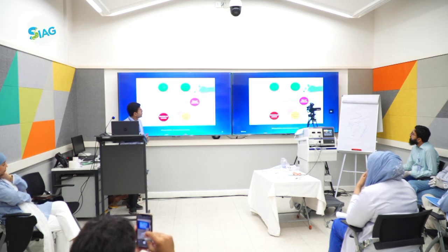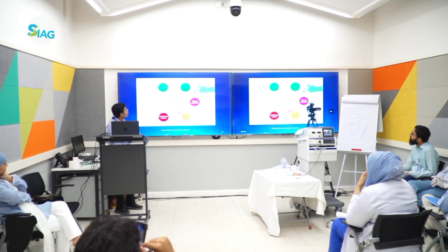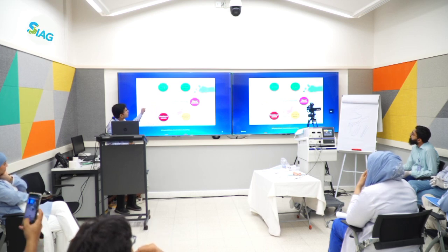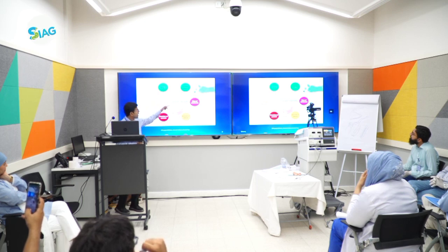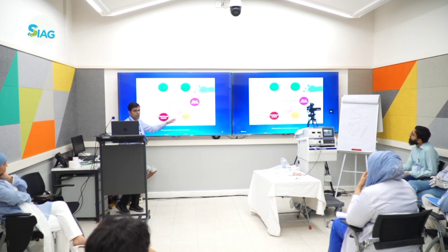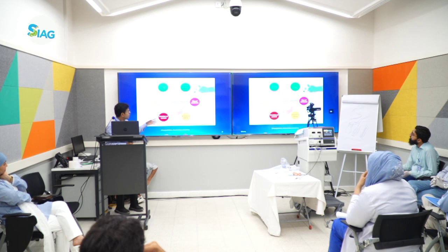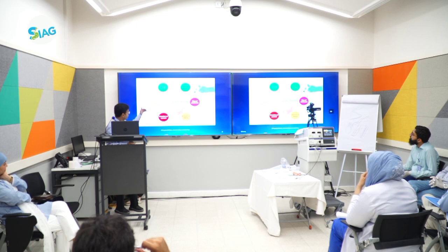There are different factors which affect current density, and obviously the amount of voltage, it's directly proportional. The frequency of the current, the size of the electrode, and the amount of tissue is again very significant. We just discussed that the less the tissue, the more the current density. The duration of current, and the resistance, which is usually at the site of the tissue.